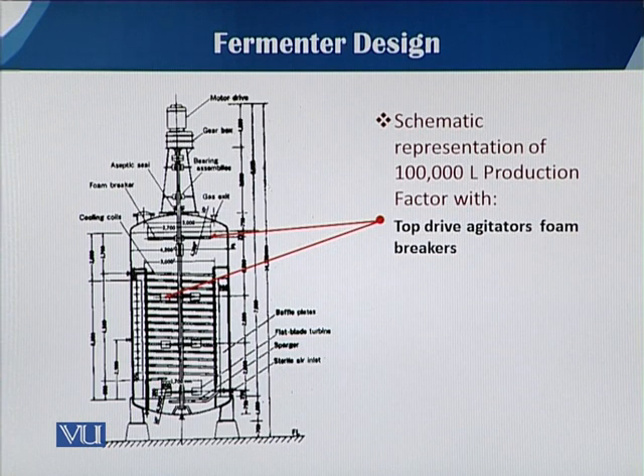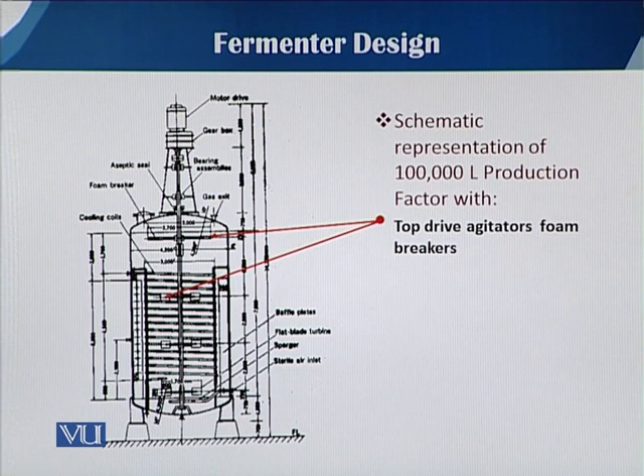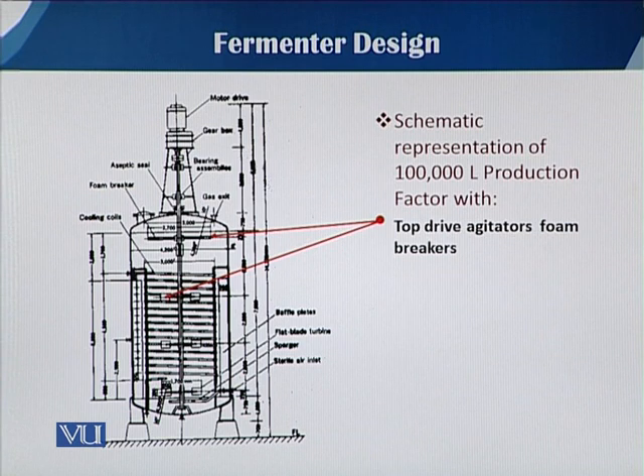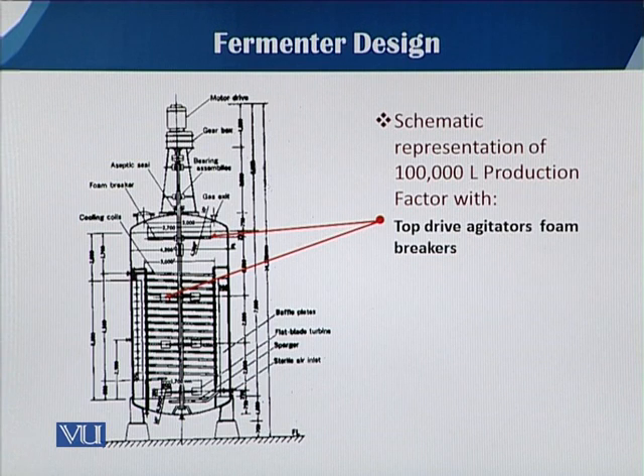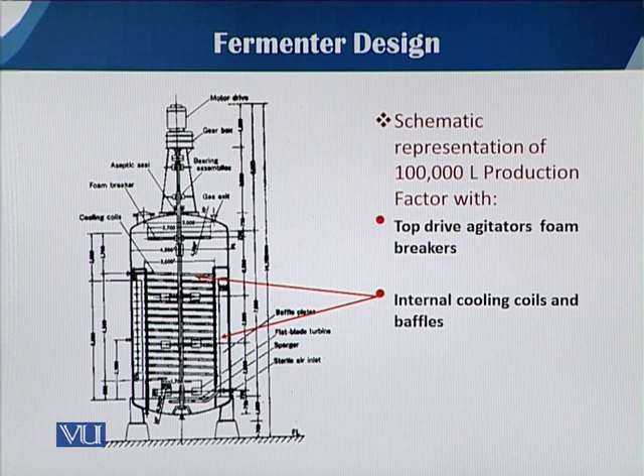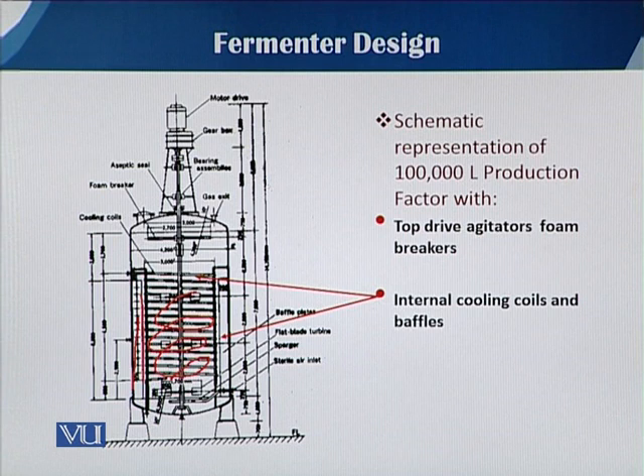If we go to large scale fermenters, you can see that a fermenter having 100,000 liter capacity has a top-driven agitator and foam breakers, because sometimes when we cannot use chemical anti-foamers we use mechanical anti-foamers or foam cutters. This provision is mostly found in large scale fermenters. You can also see that internal cooling coils and baffles are easily visible in this fermenter — these are the rounding coils and on the side there are baffles, which are mostly required in large scale fermentations.